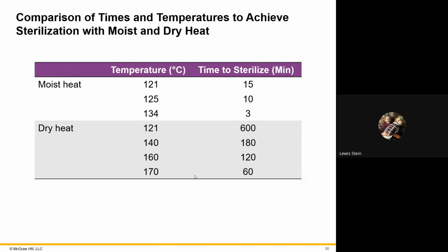When I was teaching over at West Penn Nursing School for about 5 years, we had to do all our own sterilizing. That meant me. Same deal. I did it for 30 or 35 minutes. 121 degrees Celsius at 15 pounds per square inch. The whole idea in closed systems, you will see, if you get it to this temperature, 120, which is, don't quote me, but I think about 252 degrees Fahrenheit, you're superheating the steam. And when it reaches that pressure, you can look at a thermometer on it, or just look at the pressure gauge. Those will be equivalent.